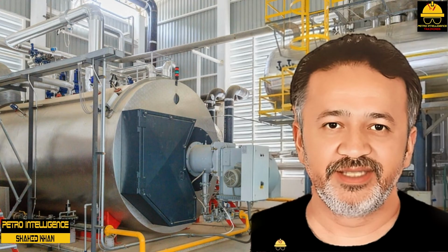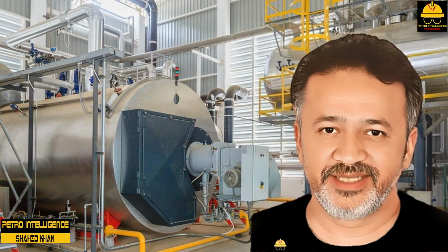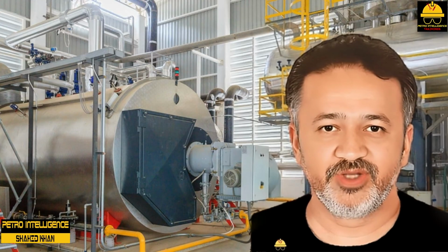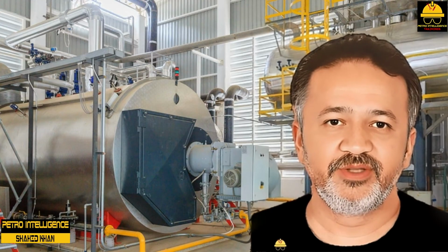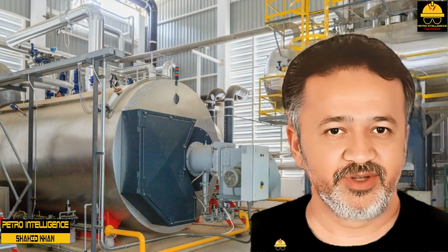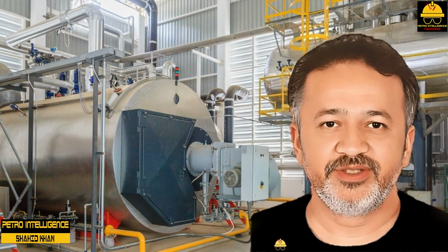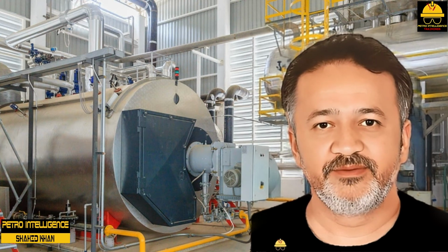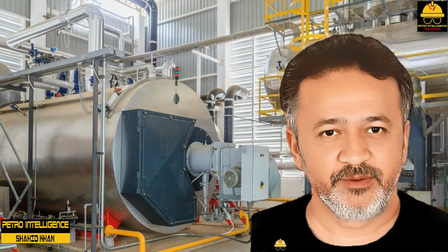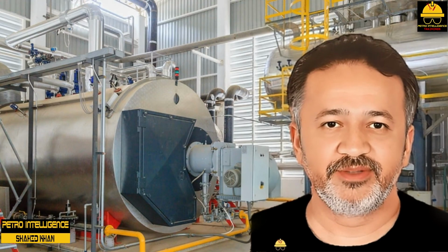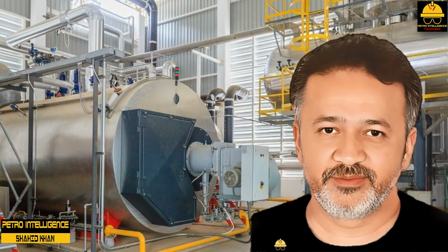Let's now discuss steam systems. Steam is used in a variety of applications in industrial manufacturing environments. There is a considerable cost incurred in the treatment and production of steam, so steam reclamation is an important and common feature at most companies that use steam in their processes. As steam flows from the boiler to the plant, it begins to cool. As it cools, condensate is formed.